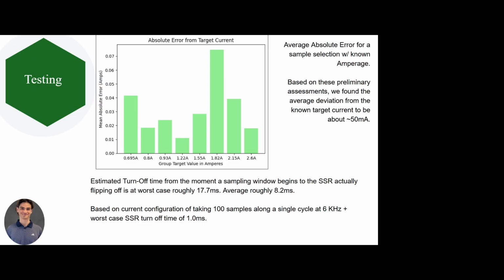but we are looking to implement a different algorithm that takes a running total of the RMS samples at each individual time point along the cycle to have a current running total, and if that current total ever exceeds the specified max, then it will flip instantly and the time will be much more dominated by the SSR itself, which would be closer to 1 millisecond. In this current implementation, the toggle time is highly dominated by the actual sampling window itself.